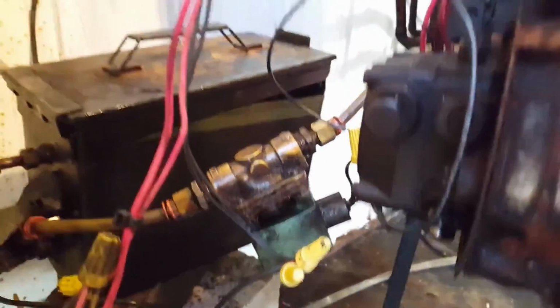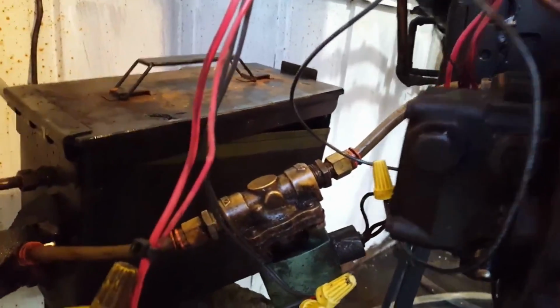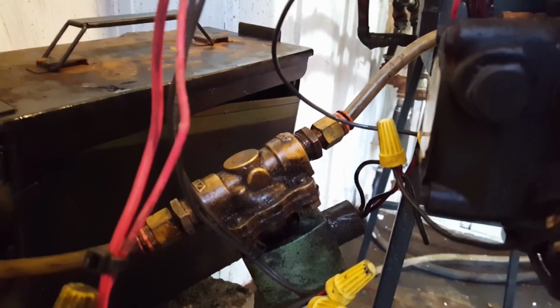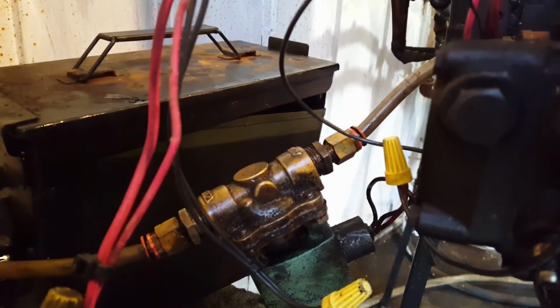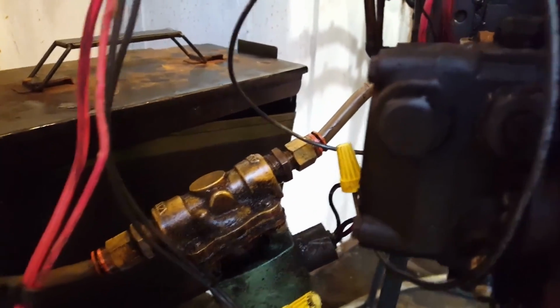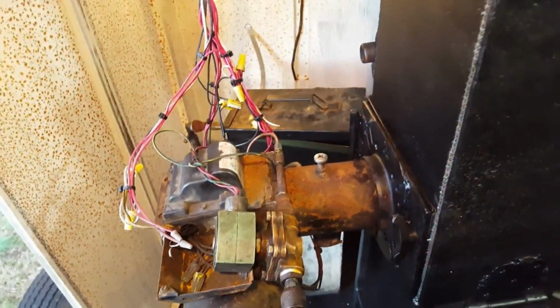And when this thing shuts off, it gets satisfied, it shuts off, that oil wants to drain back into that tank, and that valve keeps that from happening. That way, there's oil in that preheater block, and it's ready to go when it gets a call for heat. So that's the path that the oil takes.